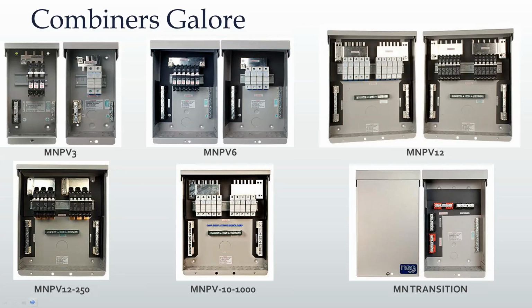The PV10 1000 is designed for use with the fuse holders and is rated up to 1,000 volts. And we have those actually from the PV3 size, which would be a PV2 1000, all the way up to the PV10 1000. So that can get a little bit confusing with all of the numbers and the different numbers of breakers that actually fit in there. If you have any questions at all, always feel free to call either our sales department or our technical support, and we'd be happy to walk you through which box will work best for your application. Yeah, good point. And there's also a nice chart on the website with the combiners that lays it out in kind of a spreadsheet form, voltage, strings, what it'll accept. So that can be pretty valuable as well.